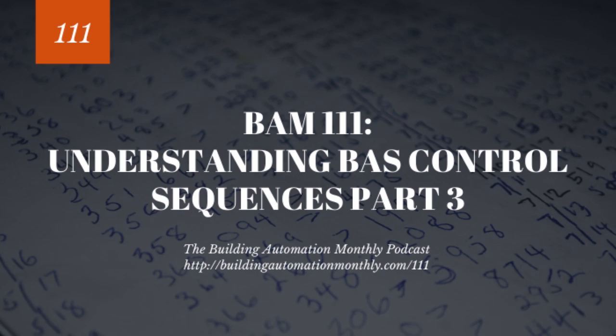The second one is FLA. A common sequence you'll see with FLA is, hey, when FLA is 90% or greater, 95% or greater. FLA is full load amps, so essentially it's the current running through the compressor or the machine, the chiller being the machine. So you'll have this chiller and you'll be measuring this FLA right around 95%, and you'll watch that for a series of minutes.